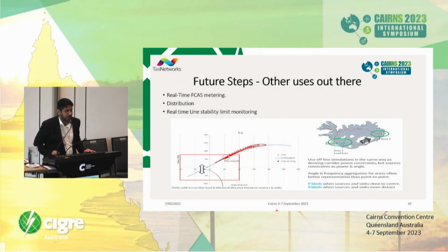We want to use PMU data for real-time voltage stability monitoring, FCAS metering, and use in distribution. There are Noja RC20 reclosers which we have in our network. We are planning to install more to have more visibility of what's happening on the distribution side. We can even monitor the real-time temperature of a line, because we can monitor real-time impedances. Using that, we can use an algorithm to figure out the current temperature of a transmission line. So there is a lot we can do using PMUs. Yep, we are looking forward to that.